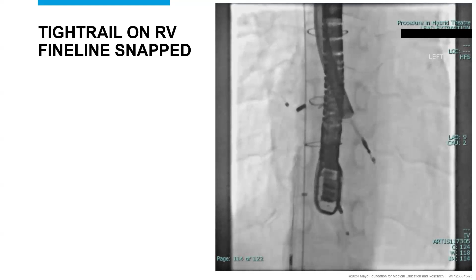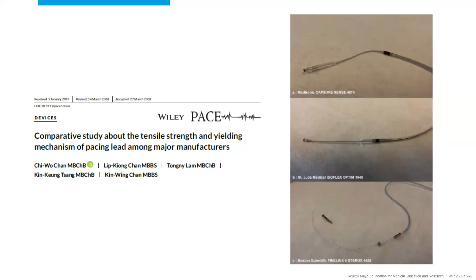And this is a nice paper looking at different leads. This is something that's quite common in the fine line leads. And actually, although it hasn't said it here, I think the older St. Jude leads as well, particularly their passive leads, will very often break off at the tip. This paper showed that it was a very common failure mechanism for the fine line lead, that it's difficult to get the tip away. I think it's usually fairly encapsulated, so even in an endocarditis case, you're probably okay from an infection point of view. It does have an impact in terms of future MRI, obviously, which is a real issue for us in all sorts of circumstances in Australia. But from a safety point of view, if you're really struggling with this, the tip breaking off is sometimes a bit of a relief, because you know that the failure has been in the lead rather than in the myocardium.